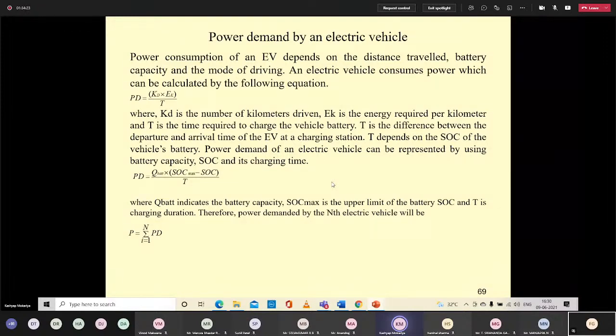So to calculate PD: PD equals Q battery, that is the capacity in ampere hour, into SOC max minus SOC, divided by T, T being the difference between departure and arrival time. Q battery indicates the battery capacity, SOC max is the upper limit of the battery SOC, and T is the charging duration.